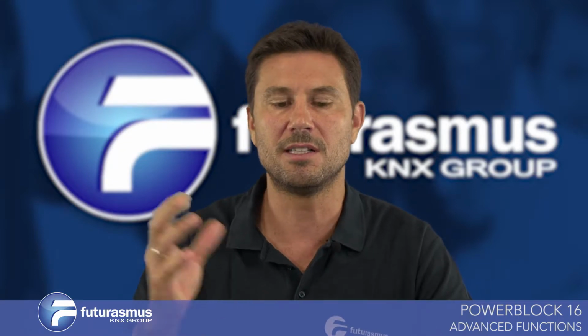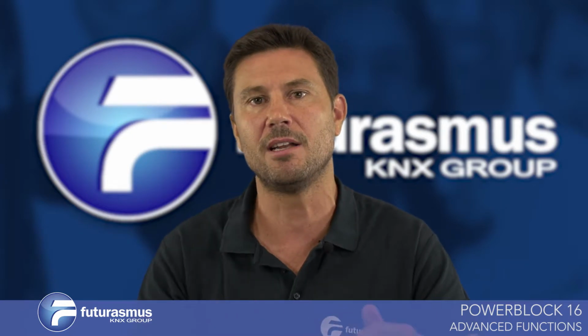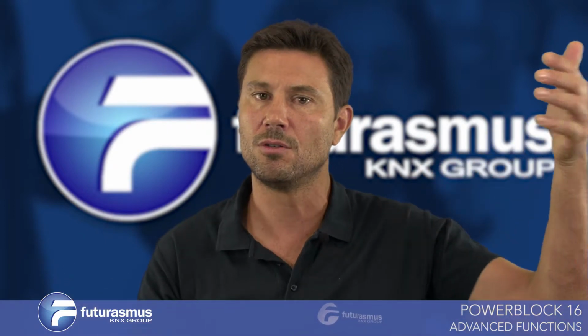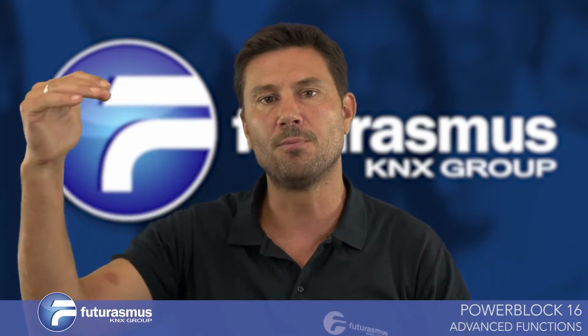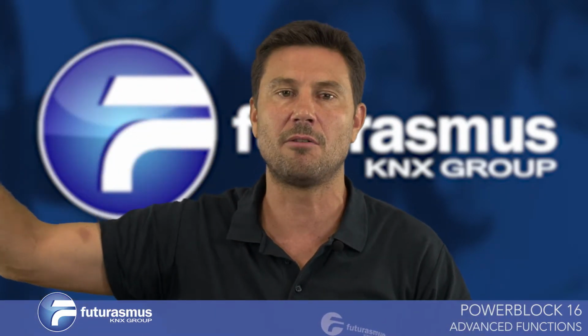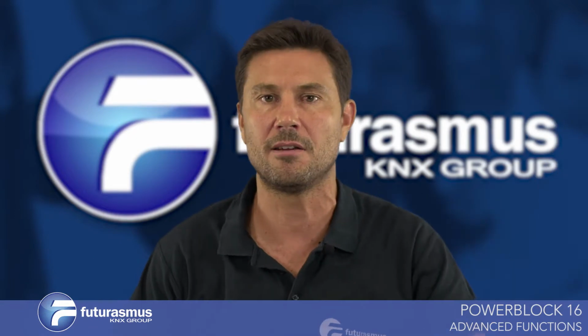So if you have PowerBlock actuators in your installation, you can use, for instance, a scene or a set point or advanced scene. I will explain now the different functions which are there. They have input objects and output objects, so you can link group addresses to the inputs, and then the output can send a telegram to the bus controlling any other actuator or any other device in the installation.